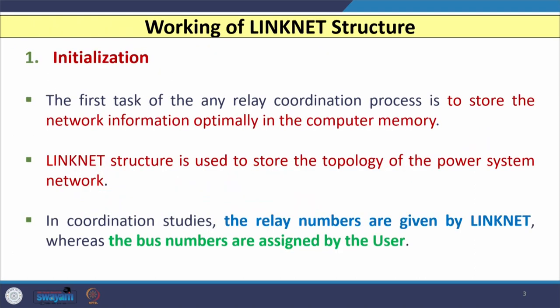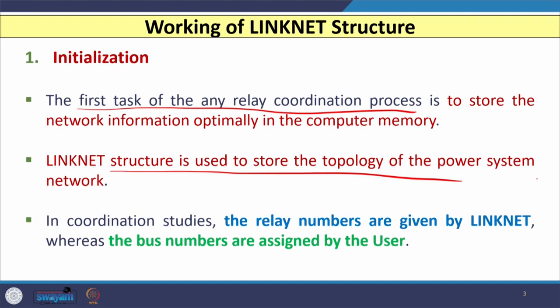With this background, let us see how the link net structure works. The first task of any relay coordination process is to store the network information optimally in computer memory. Link net structure is used to store the topology of a particular distribution network so that we can process it, calculate primary and backup relay pairs, and use those pairs for plug setting and time dial setting calculations. Relay numbers are given by the link net structure, whereas bus numbers are assigned by the user.